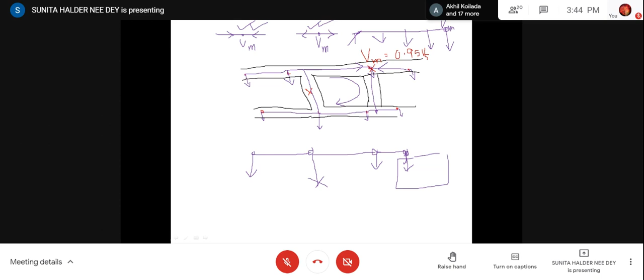So now we have to identify this minimum potential point. Why? Because for this ring main system, say here is the minimum potential point. Then as per our power transmission system laws, this minimum voltage should be available with only 5% voltage drop. So 95% of the rated voltage should be available here, right? Vs, say Vs is the supply voltage. So if it is the transformer, current will flow up to this point. So voltage drop in this part will be 5% of the rated value, which is 5% into 415 by root 3.